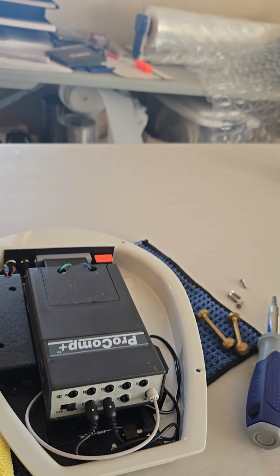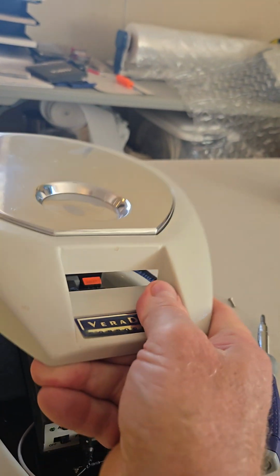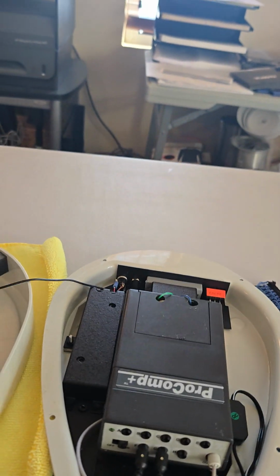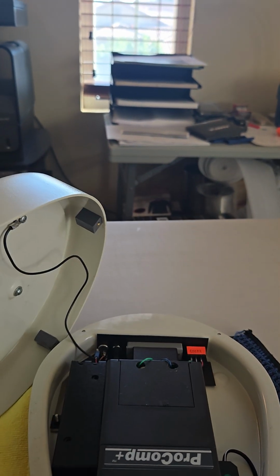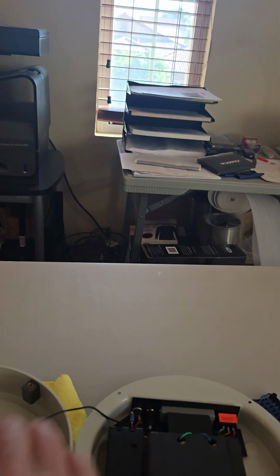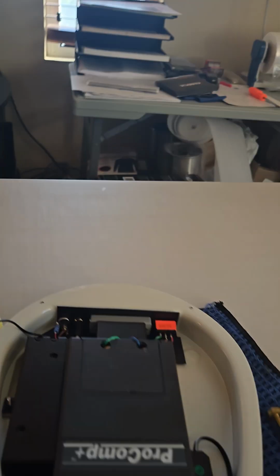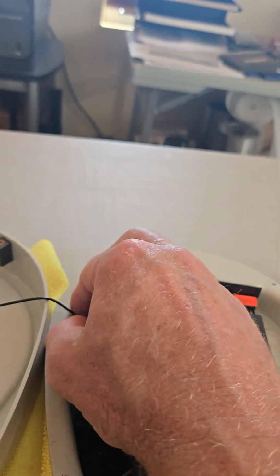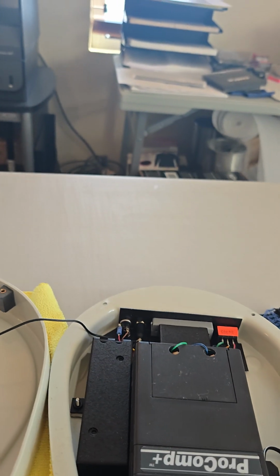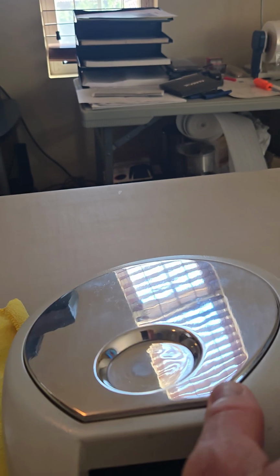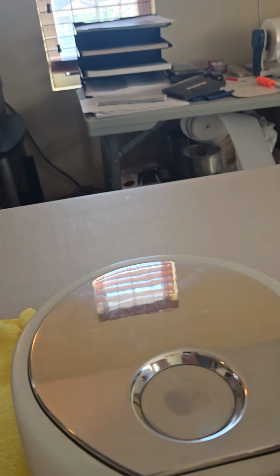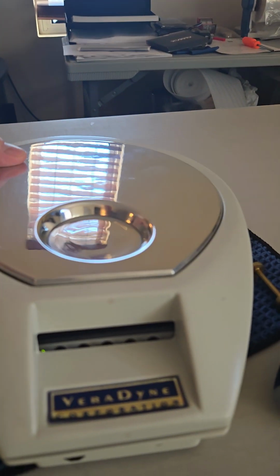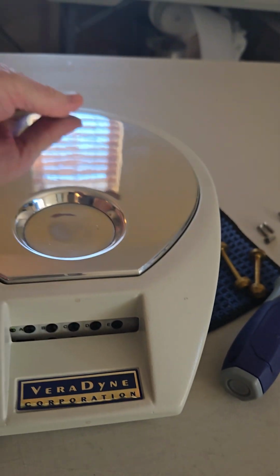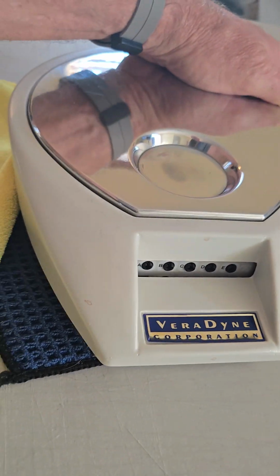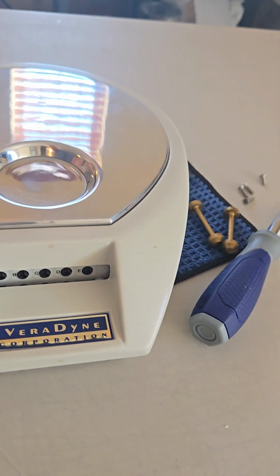Now, when you're putting the cover back on, make sure, you'll notice, like even right here, it's trying to do it. That wire in the back there, see that? It's trying to get itself underneath things. I'm sorry, my assistant took off. But you want to make sure that's not getting crimped underneath the side of the case, because it'll clip it, and that'll defeat the purpose of letting the thing get electrical conductivity to the top plate. So this goes down, and I can feel that wire underneath there, hang on one second.